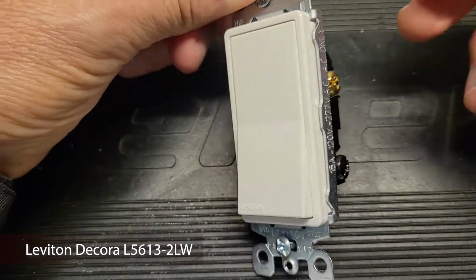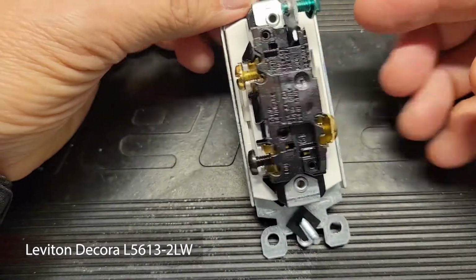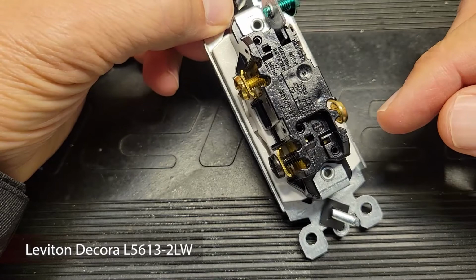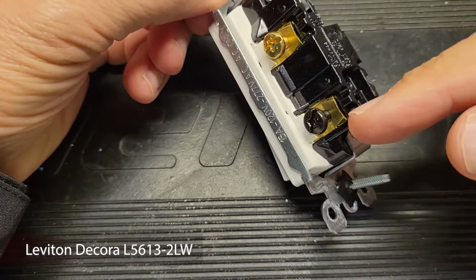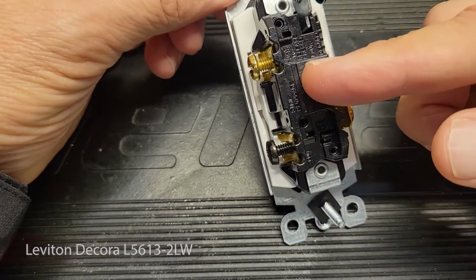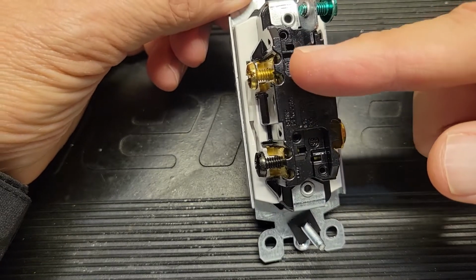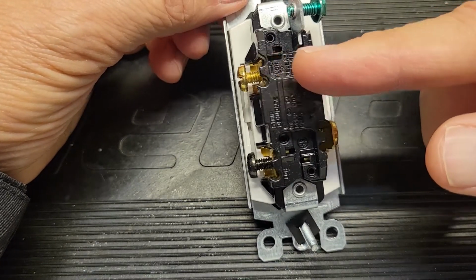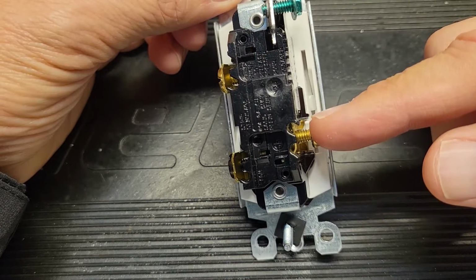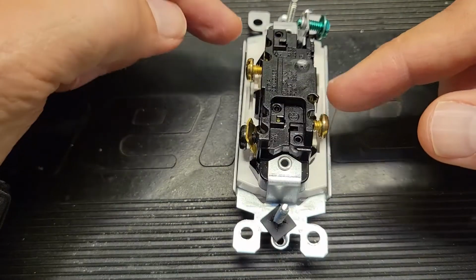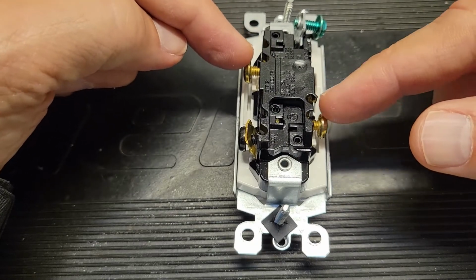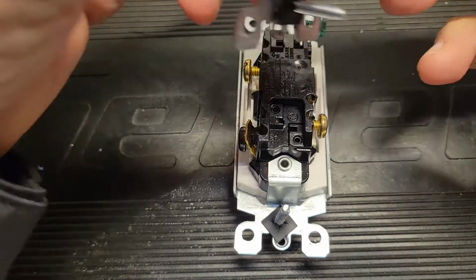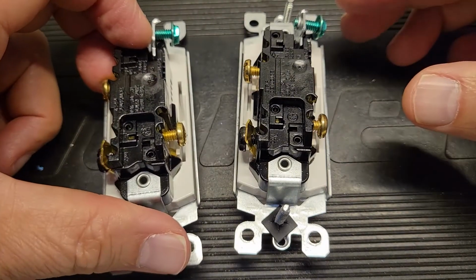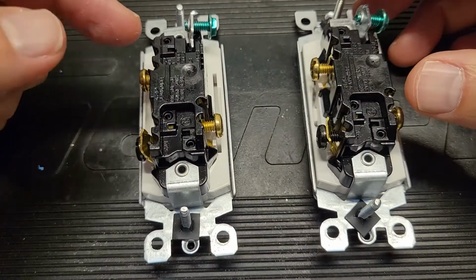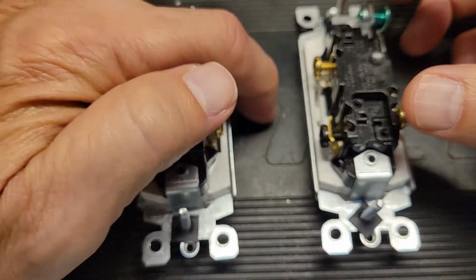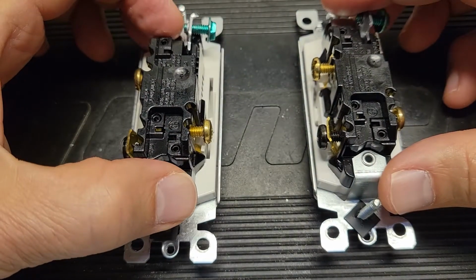In a three-way switch, you have three terminals. Energy still comes in through one, and depending on the position of the switch, either this post is energized or this post is energized. By being able to select which one gets energized, you can feed the next switch down the circuit, and therefore you can control one device with two different switches.